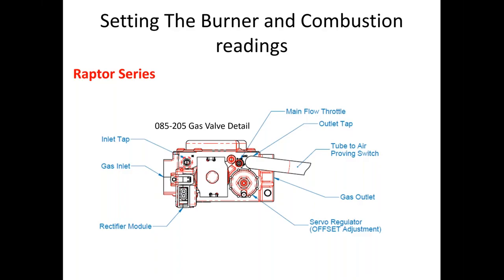There's little letters written on the side of it. That is usually one of the initial startup problems. That or the tube to the air proving switch. That sometimes is bumped off, especially during the LP conversions. And there's a screw in here that needs to get backed out 5 turns. In some of the products, some of the newer builds, we've stopped putting that screw in. That screw is fully removed. You do not need it to run.